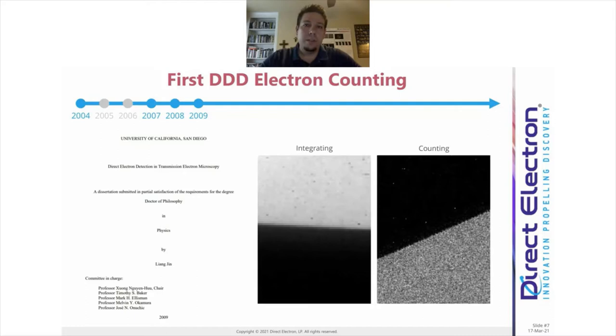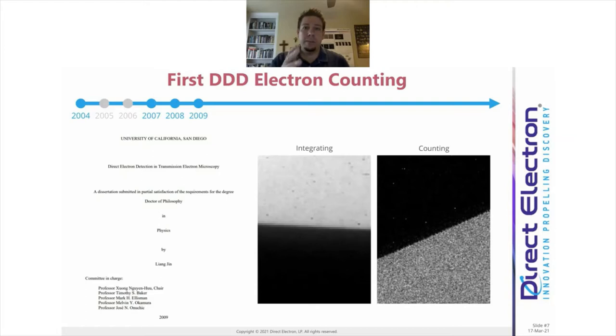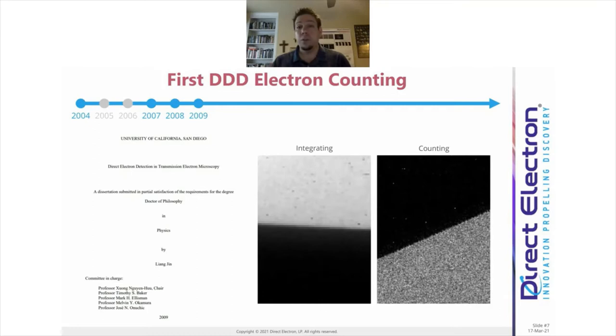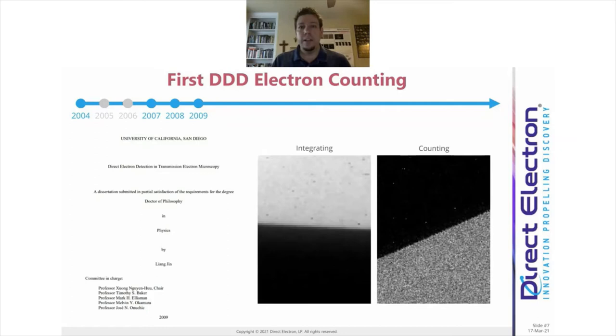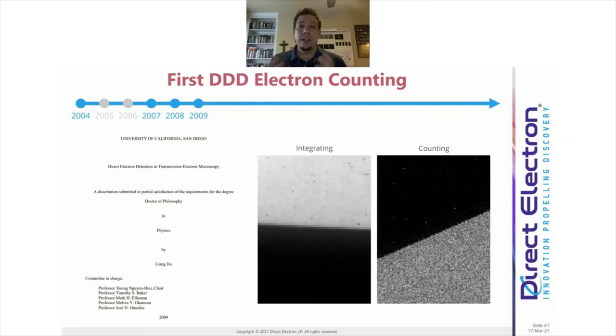This counting method was a huge benefit to the field and really improved data quality. But importantly, the way counting works is that it is basically a brute force software-based method — using integrating mode cameras that read out the full frame to a computer, where thresholding and electron counting algorithms identify each event. This requires turning down the beam intensity so that a sparse enough frame allows individual electrons to be distinguished. If electrons overlap, you can't distinguish them, limiting the exposure rate.